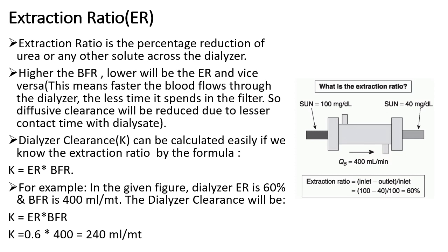Substituting the values gives an extraction ratio of 60%. From this, you can see that a higher blood flow rate results in a lower extraction ratio, and a lower blood flow rate gives a higher extraction ratio. The faster blood flows through the dialyzer, the less time it spends inside, so diffusive clearance is reduced due to lesser contact time. Dialyzer clearance can also be calculated if you know the extraction ratio: clearance = extraction ratio × blood flow rate.